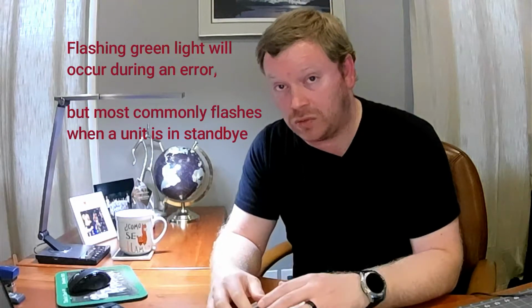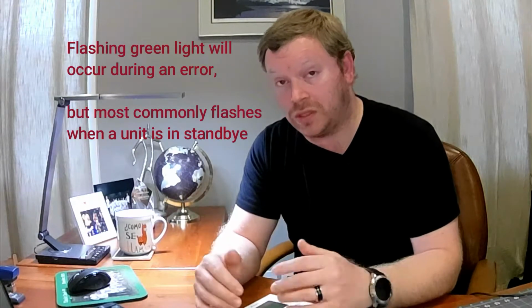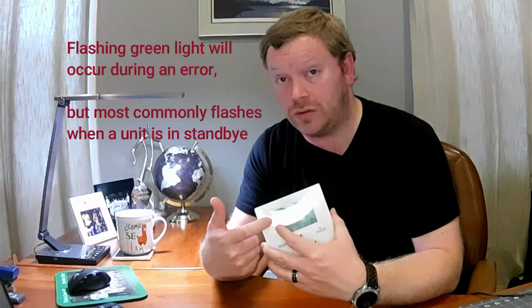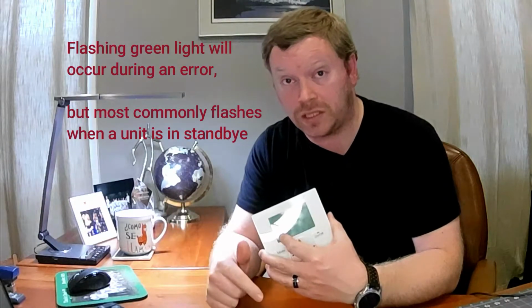The problem with that is that all of the indoor units that are maybe in the opposite mode as the master just shut off. They go to standby, but they don't operate. They don't run the fan, they don't do anything. So what happens a lot of time in the real world is a mini-split system owner is going to call and say, hey, my unit's not working properly, I see a flashing green light up at the indoor unit, there's a problem, come out, take a look, and the whole entire time it was, nope, you just had indoor units that were in the opposite mode as the master.